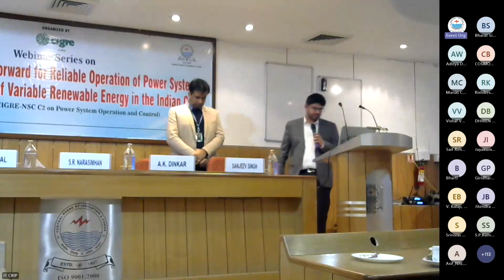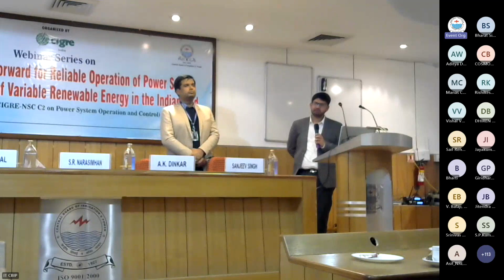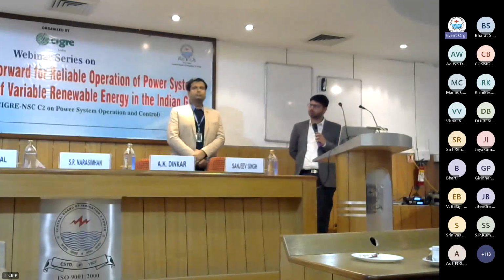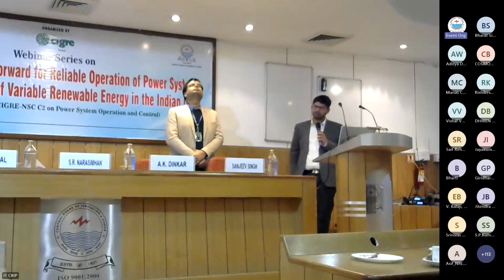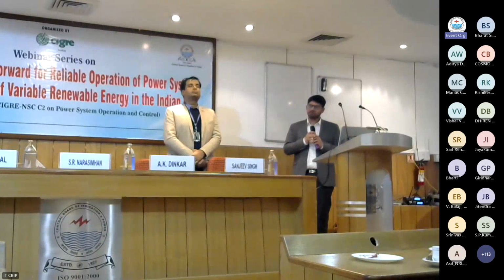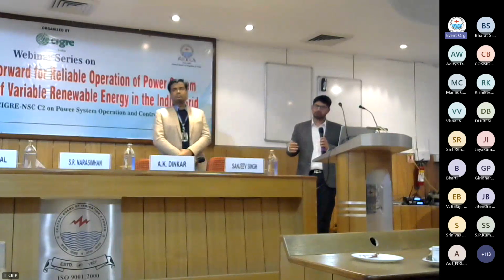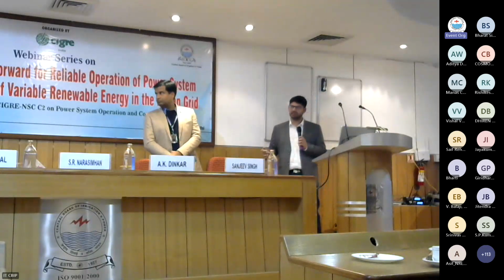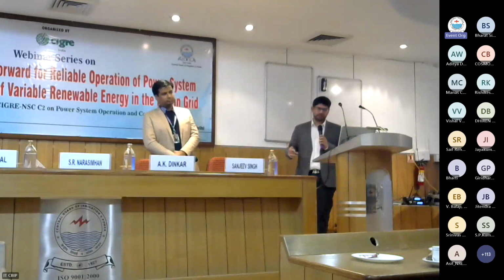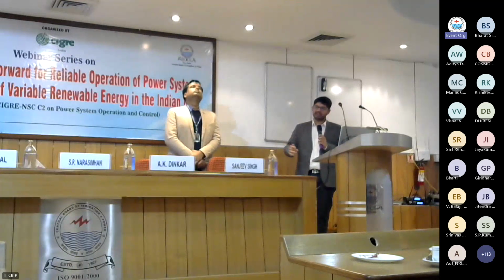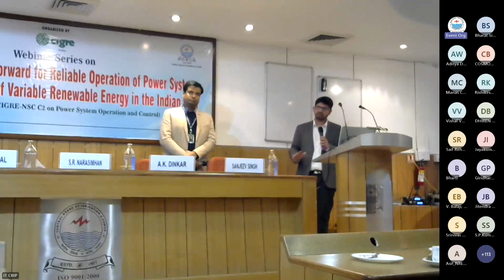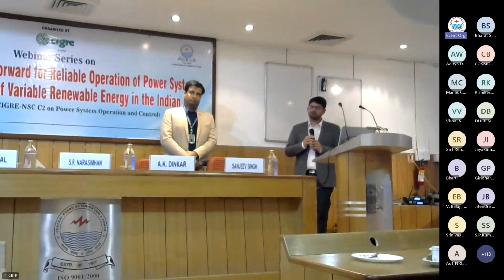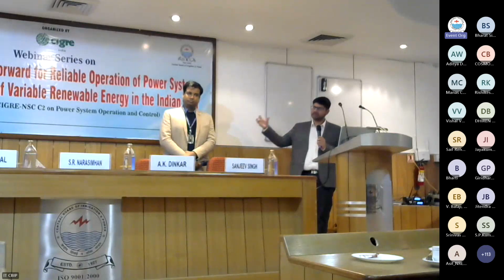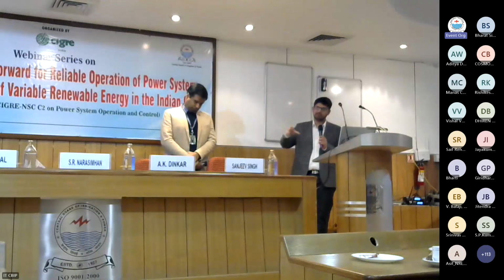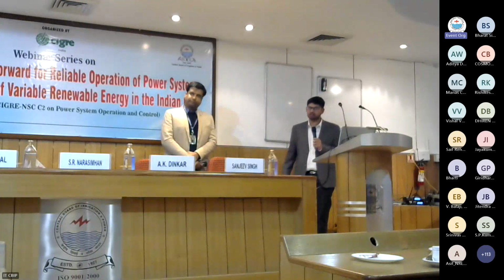The major issue is regarding the IBR level data also. So this has been the major challenge in analyzing all these events, and we have also highlighted this aspect in our report. So wherever the IBR level details were available with us, we have tried to analyze what has gone wrong. Our analysis is based on the measurement data, whether it be the PMU data or the SCADA data. We have tried to verify it against the PPC log, against the inverter logs also, whenever the data was available. But as we mentioned, the data availability has been a major challenge, and this is why we have not been able to complete the loop, going down from the POI level analysis to the IBR level analysis also.